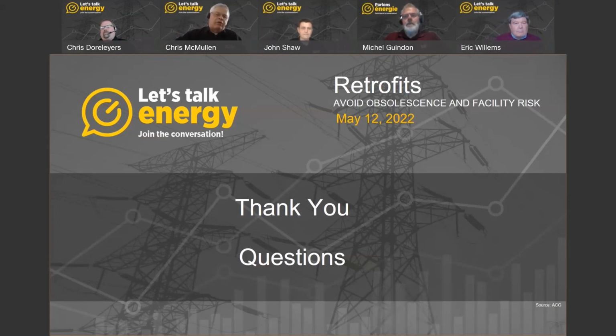Hopefully your service provider has done a good job making you aware of that. But in some cases with a 20 or 25-year-old unit, the radiator built back then wasn't built by the manufacturer directly. It was built for the manufacturer or OEM, who put the package together. So quite often when we do mechanical retrofits, we're fitting in a third party or non-OEM component. We grab the engine heat rejection data and the pump curves, and calculate what's required for a new radiator if that's the case.